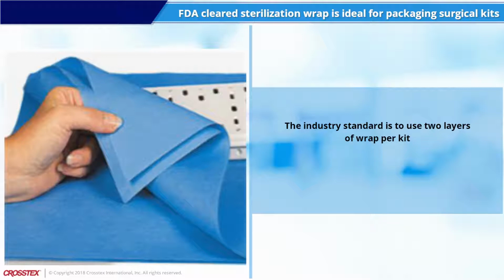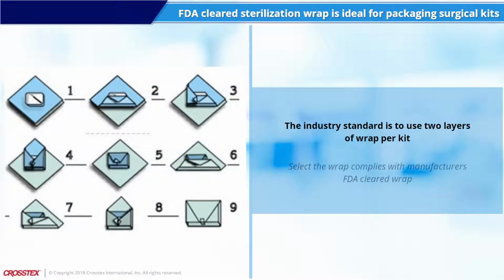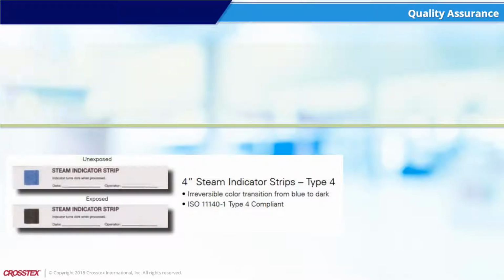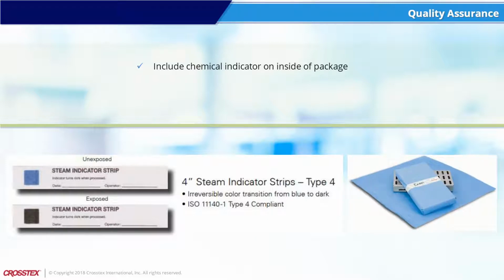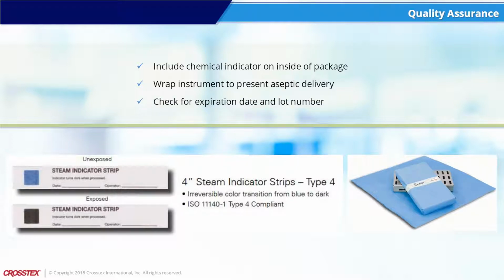FDA-cleared sterilization wrap is ideal for packaging surgical kits. The industry standard is to use 2 layers of wrap per kit. It is important to select the wrap which complies with manufacturer's FDA-cleared wrap. For quality assurance, include a chemical indicator on the inside of the wrap to verify the sterilant reached the inside of the package. Wrap in a way that allows sterile presentation and aseptic delivery of the surgical pack or kit. Check indicator for expiration date and lot number prior to use.